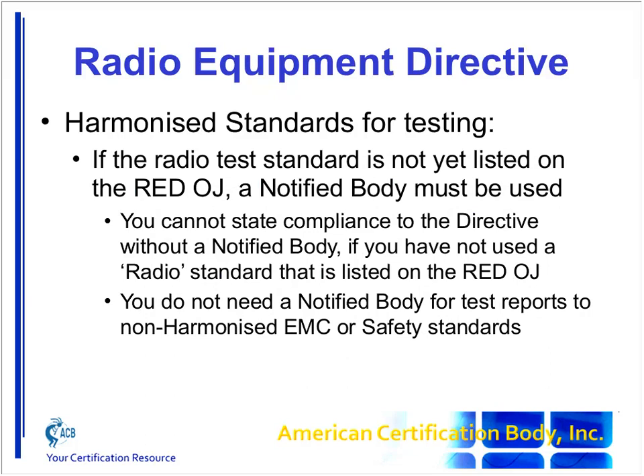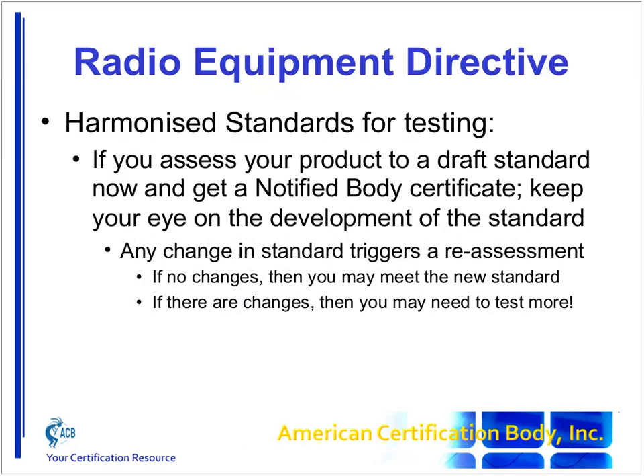If you assess your product to a draft standard now and get a notified body certificate, it's important to keep your eye on the development of that standard, because as the standard changes and develops, there might be technical changes. It might just be admin. It might be that the standard gets voted and published and displayed, and you might realize you don't need to do any new testing. You can just update the standard number on your DOC. But if you're testing to a draft standard, do keep your eye on the development and do keep close to ETSI, just in case the test cases change.